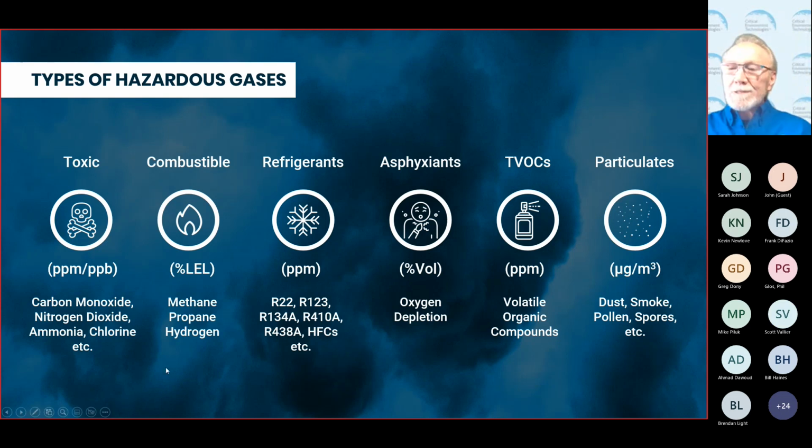So if you walk into a room that has been filled up with CO2 from a leak in a tank of CO2, that room fills up quite rapidly, number one, because that CO2 is under high pressure and there's a high volume in that tank. And number two, it's heavier than the ambient atmosphere. So even though it's mixing with the ambient atmosphere, the highest concentrations are going to be at the lowest point in that building envelope, the area that you're going to fall into.